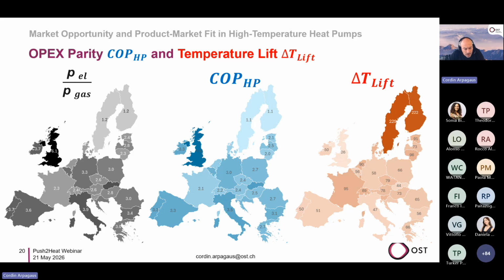Now we can convert this with the fit function to an economic COP. And this is now shown here in this map. And now the third map is the temperature lift. So as an example, in Switzerland, you can see it, the numbers are a little bit small there, but the price ratio in Switzerland is about 2.4. This gives an economic COP of 2.2. So the COP has to be higher than 2.2, and this is related to the temperature lift of 89 Kelvin.